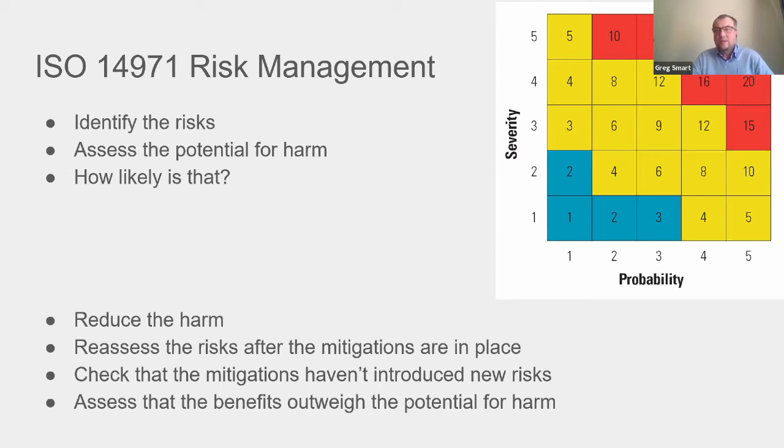You could also consider what they call labeling. In the context of medical device software, labeling really means anything to do with the UI. So the way in which your fields are named, the way in which tooltips are displayed, the way in which forms are arranged. These can all be used to mitigate risk of harm. If misuse could lead to harm, you can look at ways of designing your UI to avoid misuse.